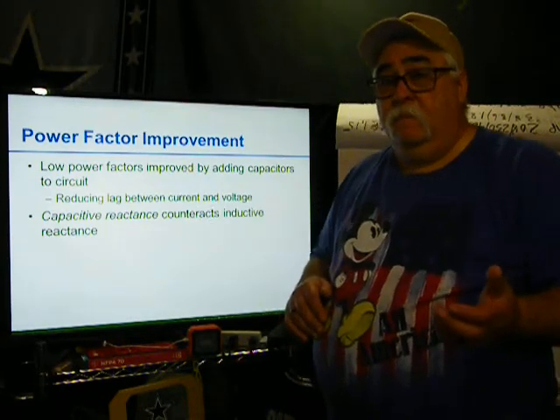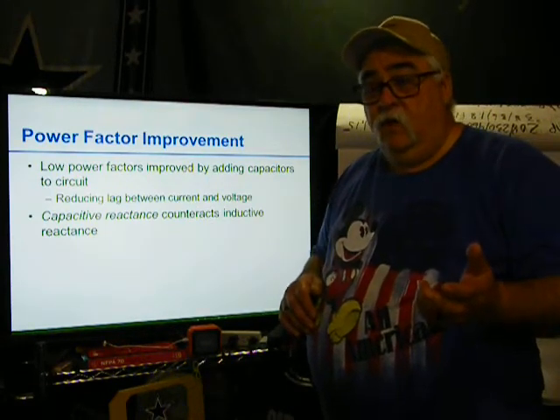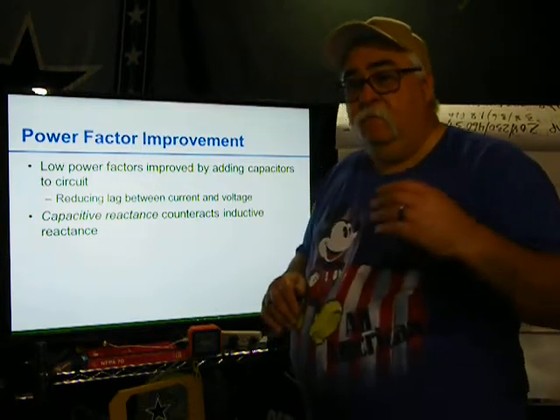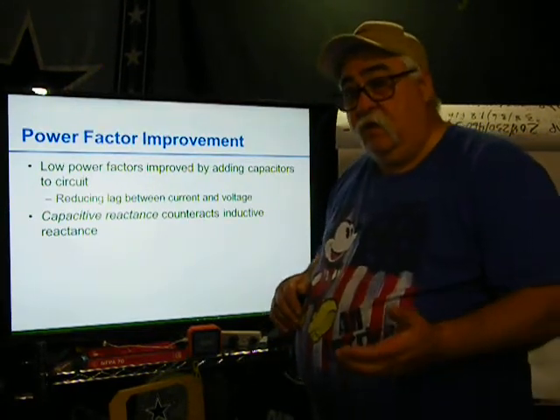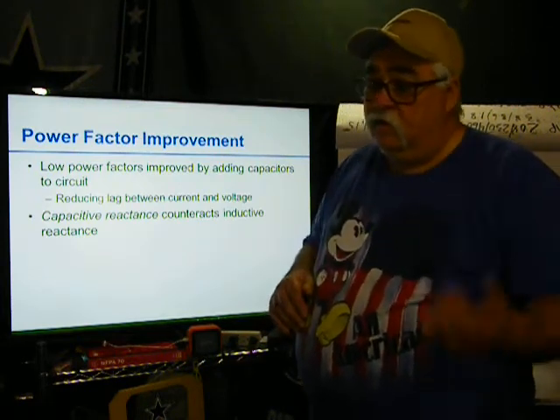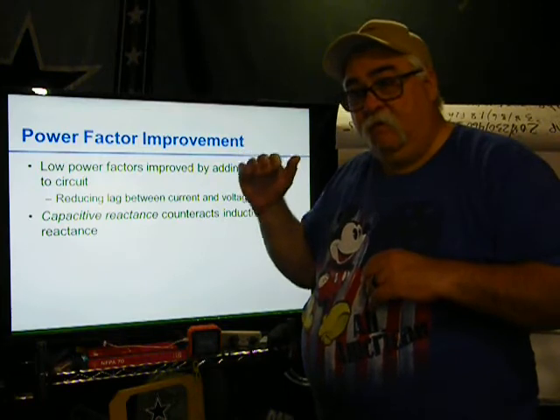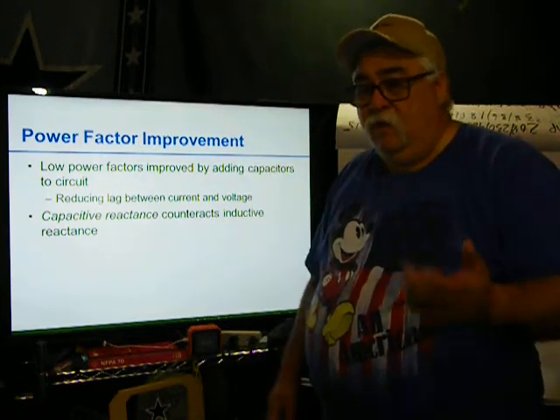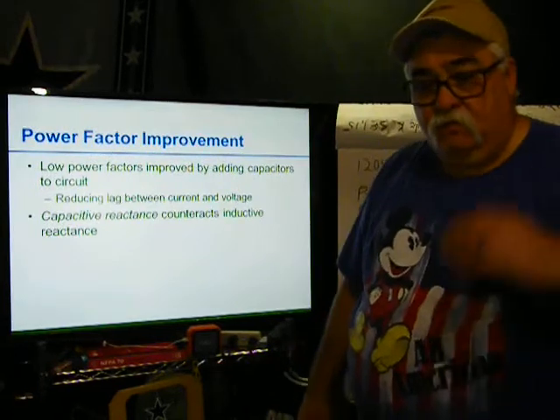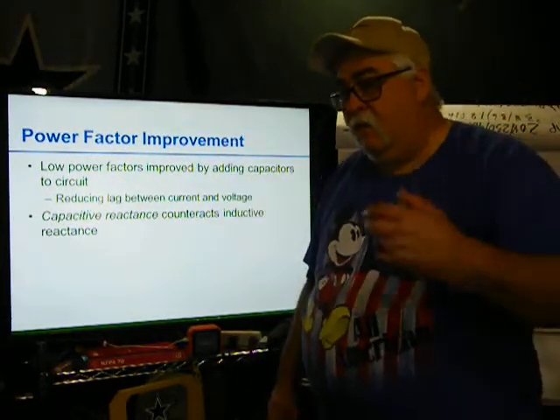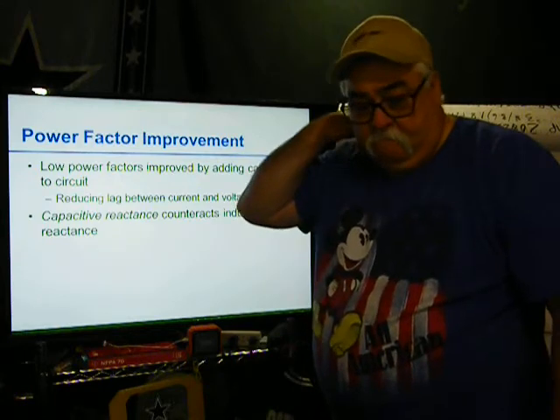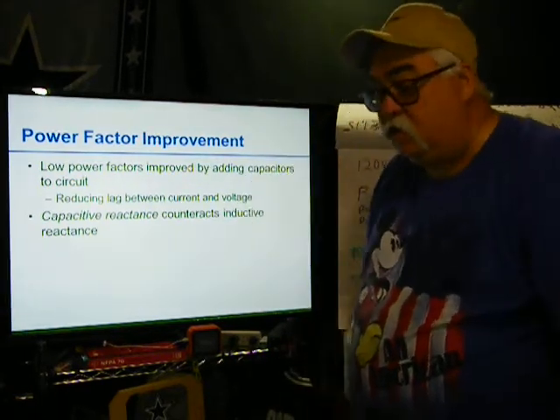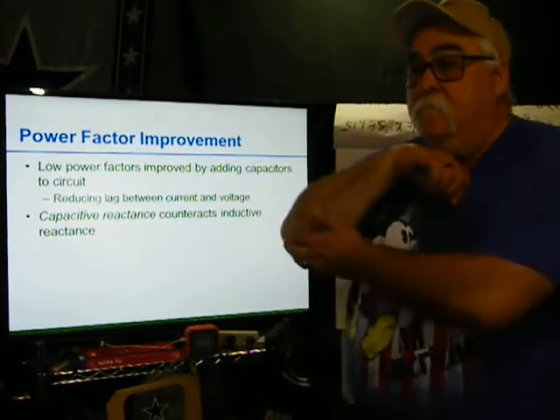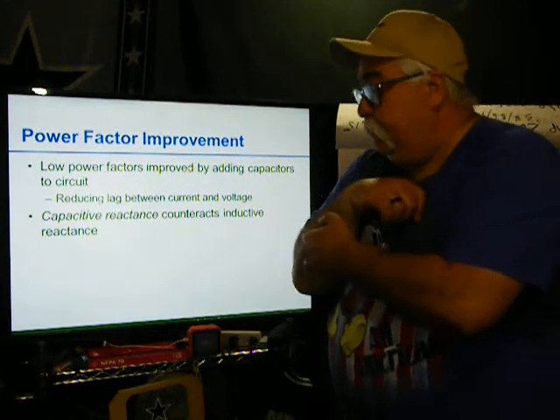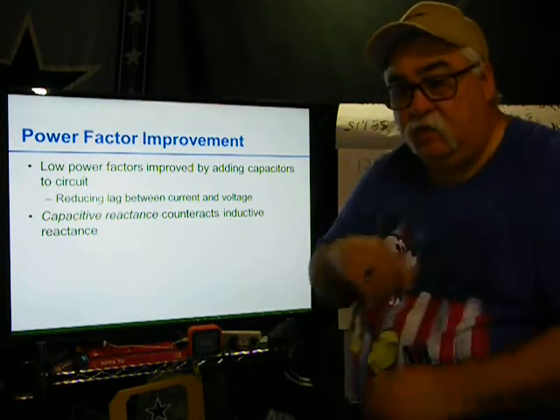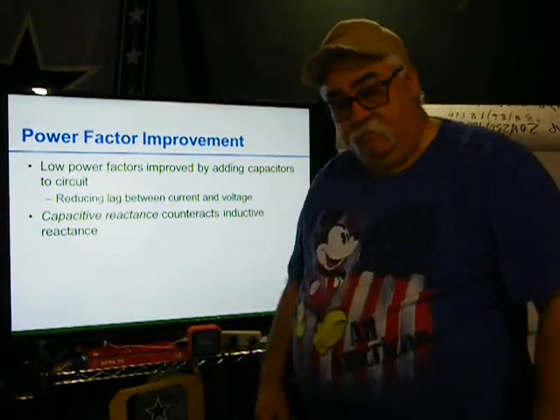Utilities don't want to pay double the electricity when there's a way to correct it. So the engineer or the electrician that's doing it, it's their job to make sure to maintain that power factor above 90%. It also creates problems with motors. If you start getting a lot of dirty power, it affects electronics and everything else. That's a different chapter. There's more on it in the industrial book, where we start talking about harmonics and everything else. We don't have it in this book. We'll get into it in another class.